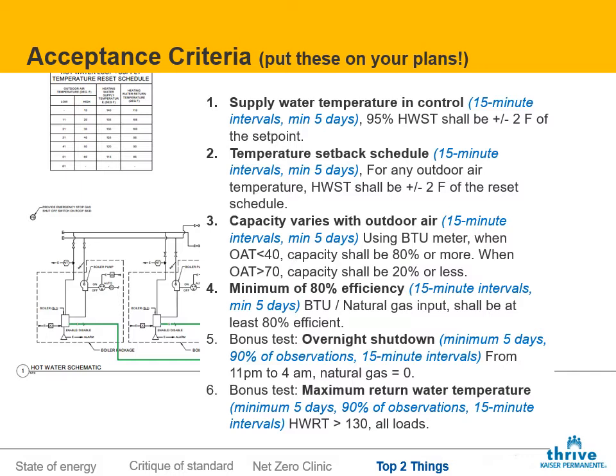Right. Third, I expect to see the capacity of the overall boiler system vary with outdoor air. This seems like a really simple concept, but trust me, when you start looking at data, nothing is simple here. But think about it, when the outside air temperature is less than 40 degrees, we should be using more natural gas in that hour than when the outside air temperature is 70 degrees or 80 degrees, right? When the outside air temperature is over 80 degrees, really we should be off or seeing very little boiler usage.